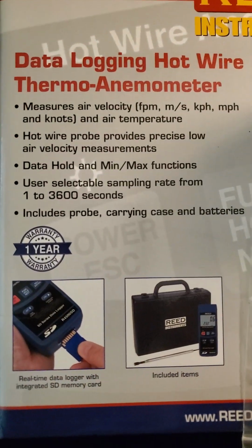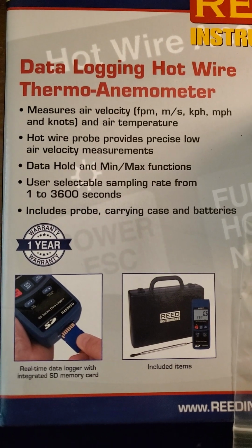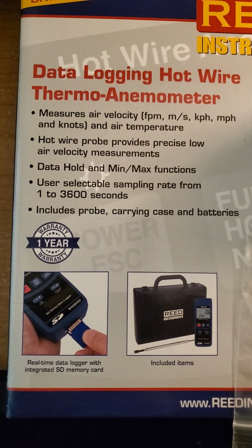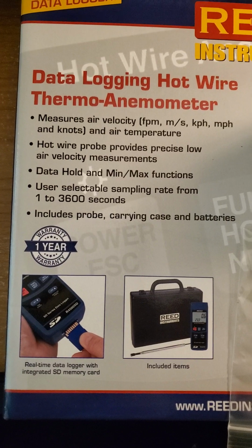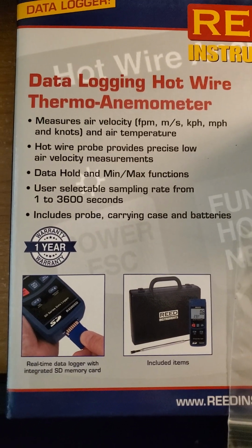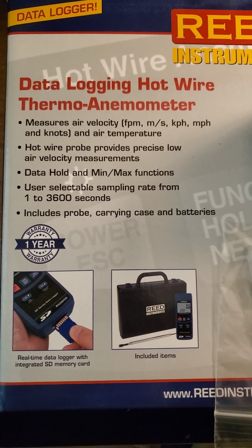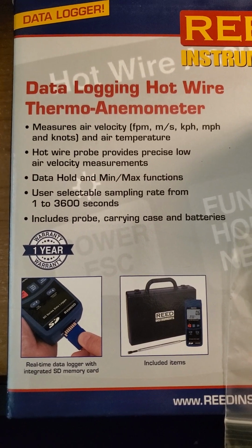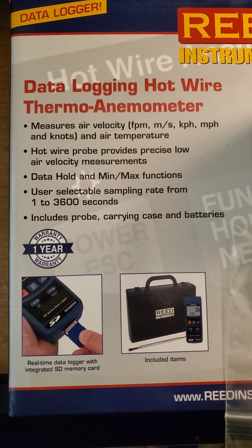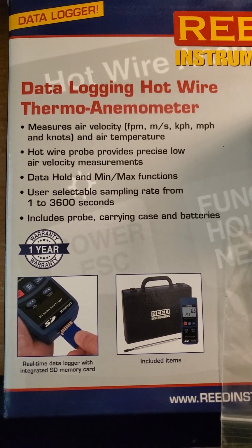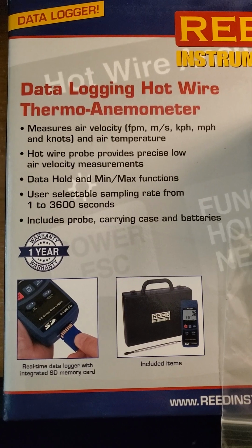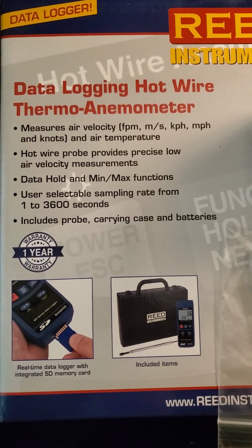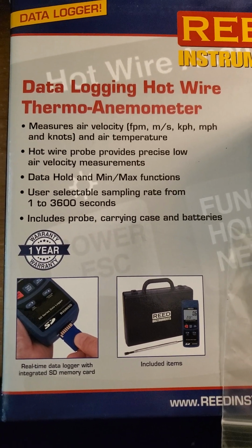It measures air velocity in feet per minute, meters per second, kilometers per hour, miles per hour, and knots, as well as air temperature, probably ambient air temperature. It has two separate probes: one is the hot wire, the other is a thermistor to measure the temperature of the air. They're both on the probe.